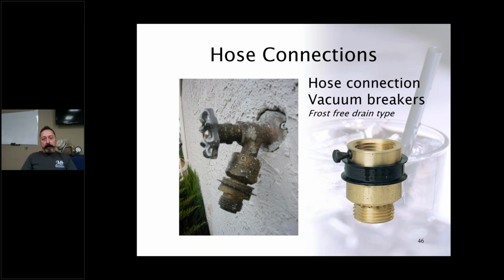Some small water systems only consist of residential housing, in which case, as far as private buildings, the only cross connections we need to worry about are the outside hose bibs. We can have two methods of controlling those. On older buildings, they'll have these hose bibs that you're looking at there. You can thread on a hose connection vacuum breaker, and that will protect anything from getting sucked into the water supply through backsiphoning. So if that had been on our deer hide incident, that would have never occurred.